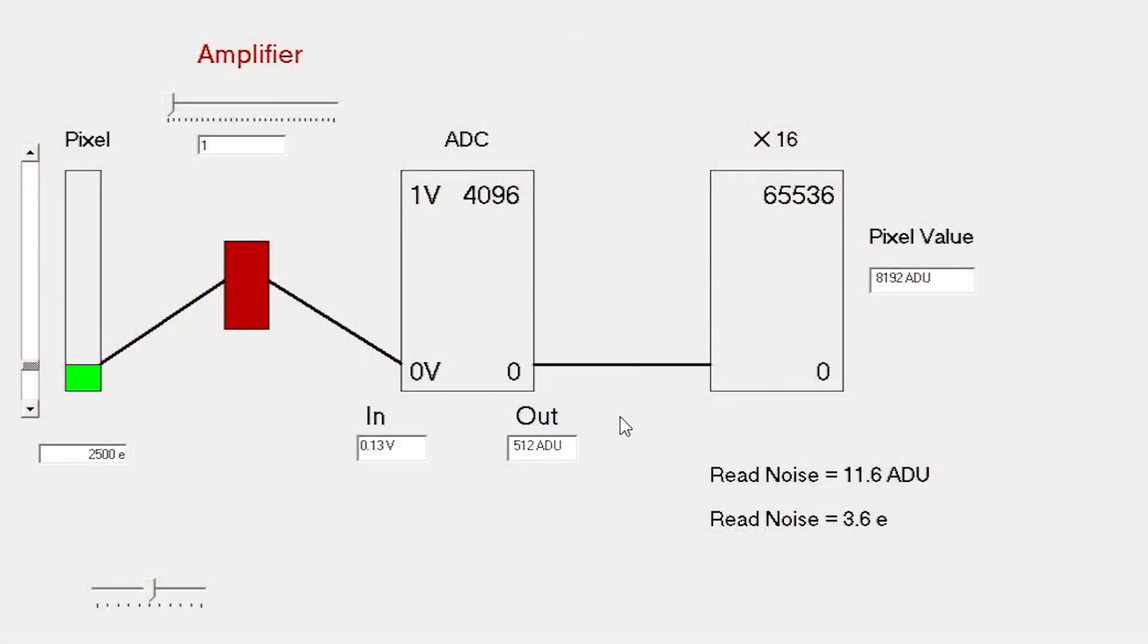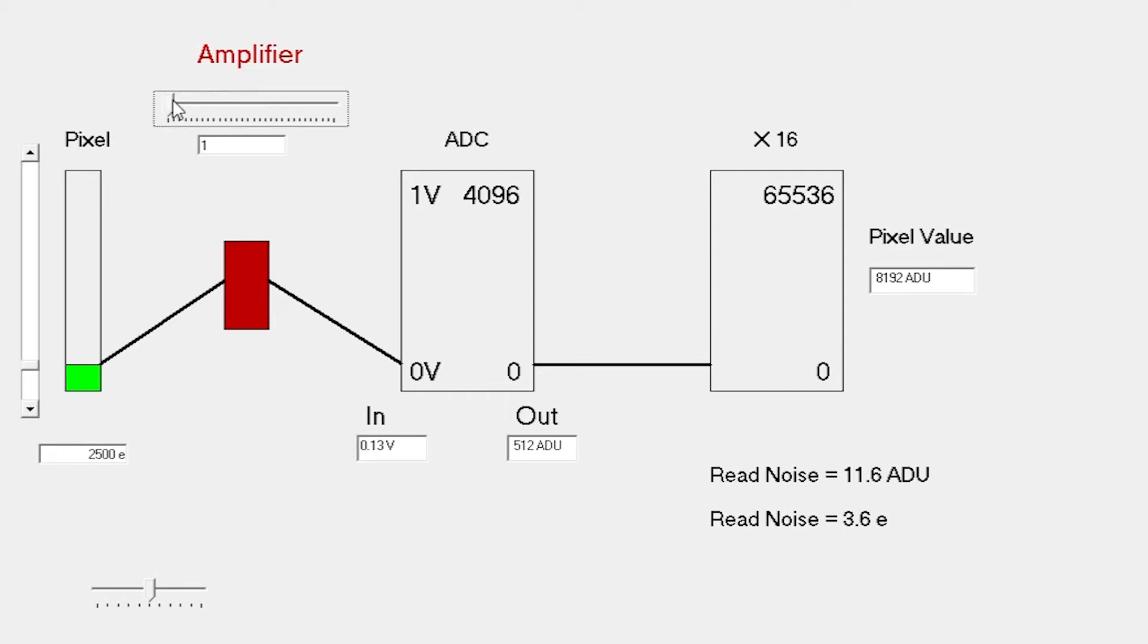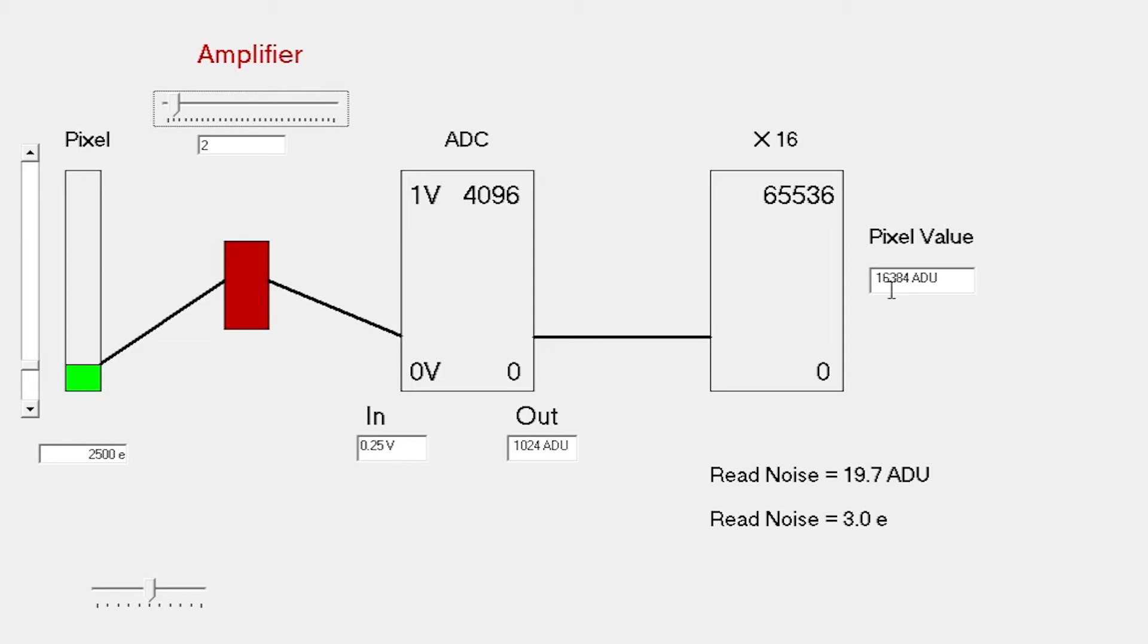Let's look in detail at what happens when we change this gain. If we look at the situation where we have 2,500 electrons corresponding to an output pixel value of about 8,000 ADU units. If we were to increase the amplifier gain by 2, by a factor of 2, we then have a pixel value that's increased twofold, so it's now 16,000. Our signal has increased by 2 times. We'd expect what would happen is that the noise, the ADU standard deviation of the read noise, would also increase 2 times because we've increased the gain 2 times. However, the interesting thing that happens is that the read noise actually increases a little less than 2 times.